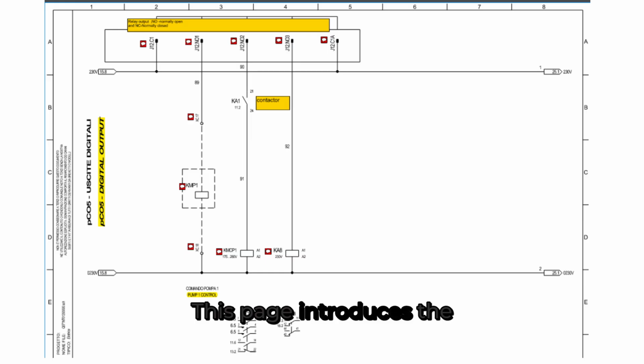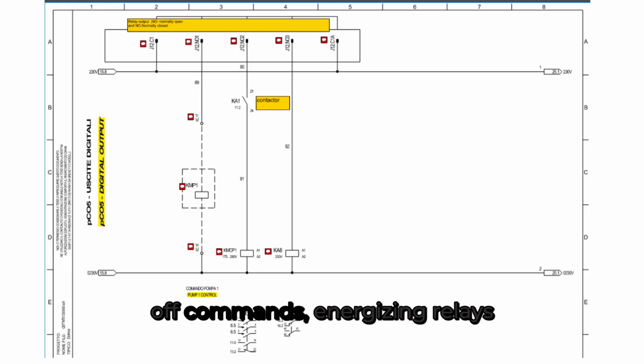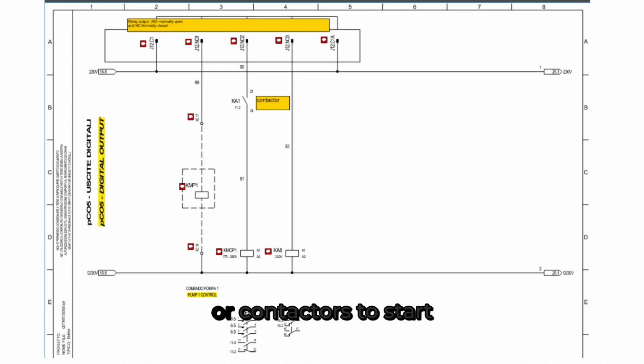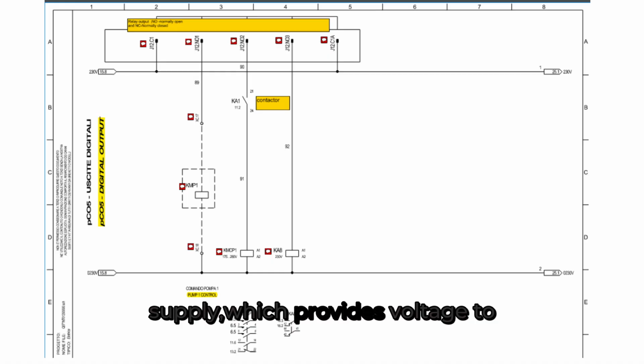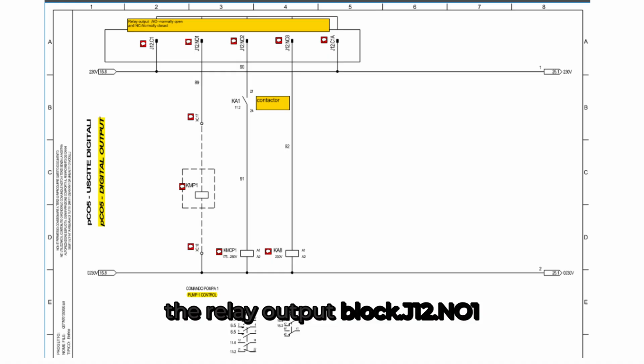This page introduces the digital output section of the Carel PCO5 Plus controller. Unlike analog outputs that send variable signals, digital outputs act as on-off commands, energizing relays or contactors to start and stop field devices such as pumps, valves, or fans. At the top, we see the 230-volt power supply, which provides voltage to the relay output block.